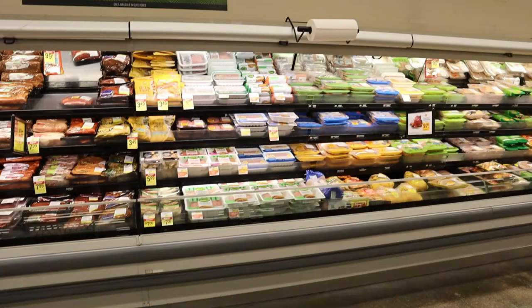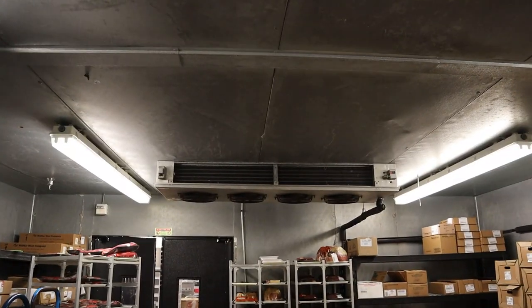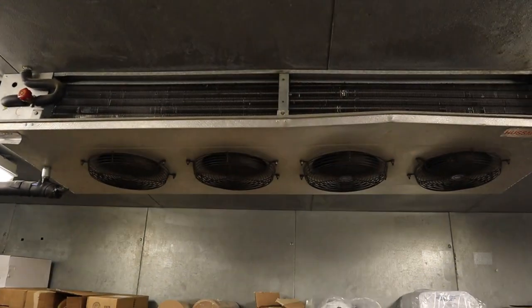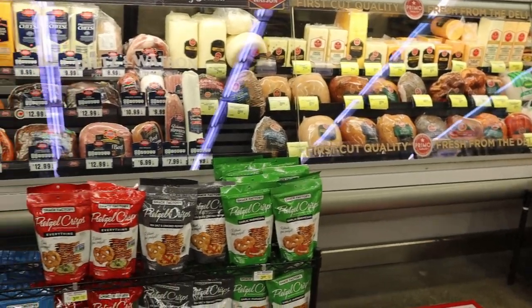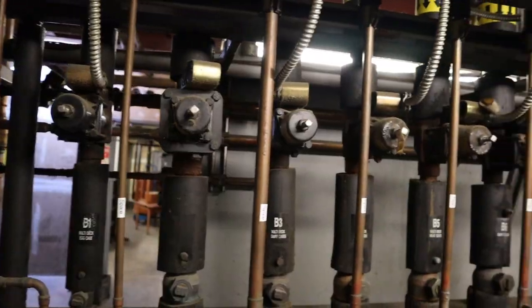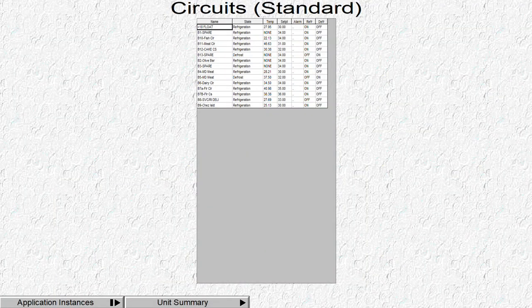The product that runs off the plus 18 is anything that runs 27 degrees — so the meat cases and the meat cooler. Anything really with meat and deli will be on the plus 18. Also service deli, but if it runs too cold, that's why they have the EPR, the sport valve, so they can adjust it and make them a little bit warmer as needed. And these are all the circuits tied into that plus 18, as you can see.